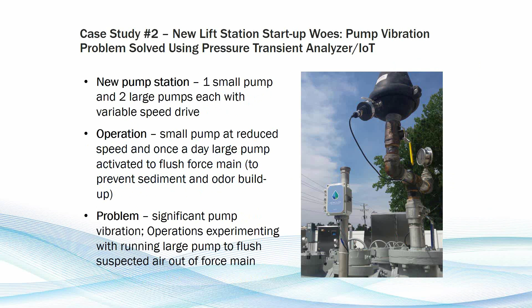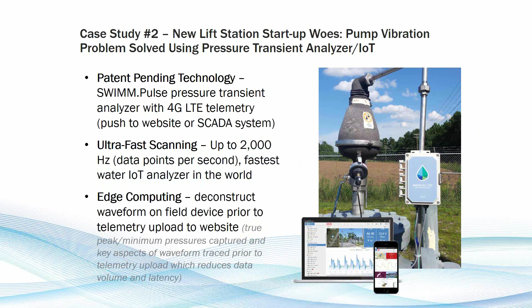So I just wanted to show you real briefly a little bit about the technology that was used. The SWIMM.Pulse Pressure Transient Analyzer is a unique IoT technology with 4G LTE communication, with data being uploaded to our Swim Connect website. It could also be upgraded or uploaded to a SCADA system. But what's really unique about the system is its ability to scan fast, up to 2,000 hertz, or data points per second. This is really the fastest water IoT analyzer in the world. We're also performing some edge computing. We're deconstructing the waveform, trying to tease out specific information. We really don't want to try to upload 2,000 data points per second to a website over the cellular network. That's just not practical. So we tease out specific information by deconstructing that waveform, which you'll see in the next chart.